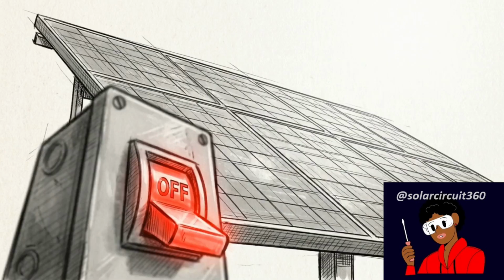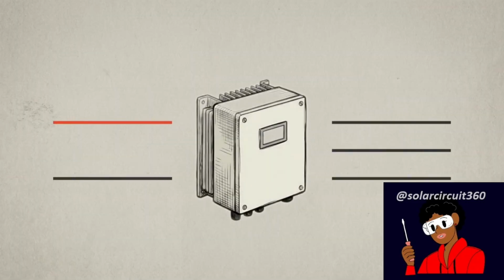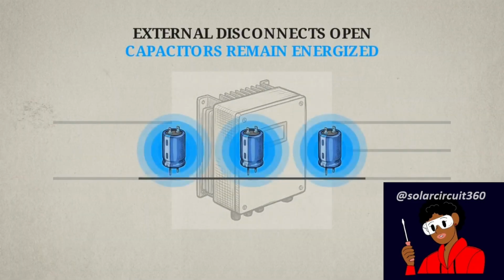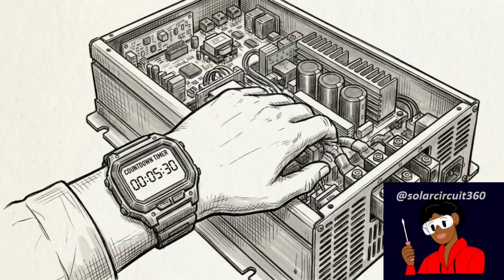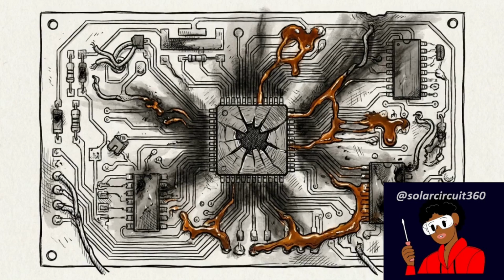Solar panels maintain lethal voltage as long as they are exposed to light, regardless of the disconnect switch position. Large hybrid inverters often contain internal capacitors that hold a charge after shutdown. These must be allowed to discharge fully before any testing begins. Testing without total physical isolation risks turning a safety check into a total system failure.